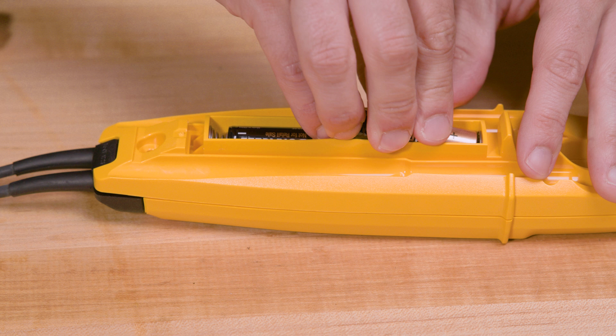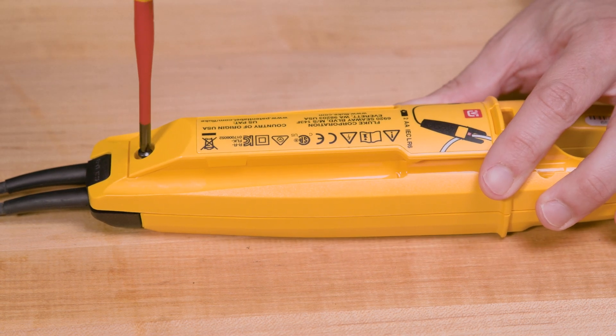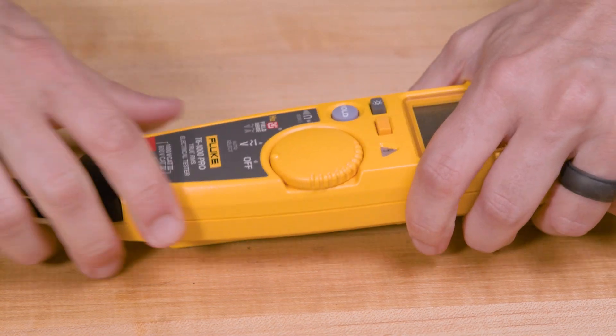These testers come with a safety feature that secures the leads in place, reducing the risk of accidental disconnection or shocks. Once the new leads are in place, check the connections — make sure they are secure and the leads are not loose or wiggling. You can also verify the integrity of your test leads by performing a simple ohms measurement to confirm they are electrically reliable and able to carry a signal within allowable loss parameters.